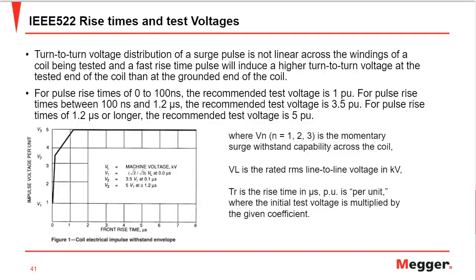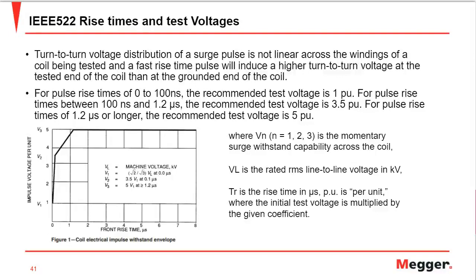So here we have the exact standards. For 0 to 100 nanoseconds, the recommended test voltage is 1 times, or just the per unit value, of that motor. For pulse rise times between 100 nanoseconds and 1.2 microseconds, the recommended test voltage is 3.5 per unit, the rated terminal voltage. And if it is longer, more than 1.2 microseconds, we use five times the per unit terminal rated voltage of the motor as the test voltage.